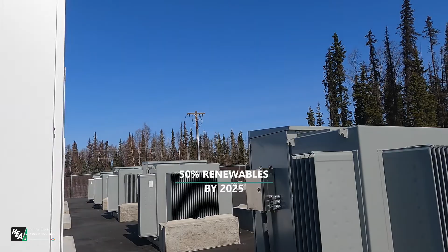While hydroelectricity output can be controlled, wind and solar energy vary from day to day and minute to minute. Regulating renewables that are unpredictable by nature is challenging. HEA's BESS can go from zero input to full input in 1/10 of a second, and it can regulate faster than any thermal or hydro unit. So it gives you a world of capability for renewable power that HEA would not otherwise have.